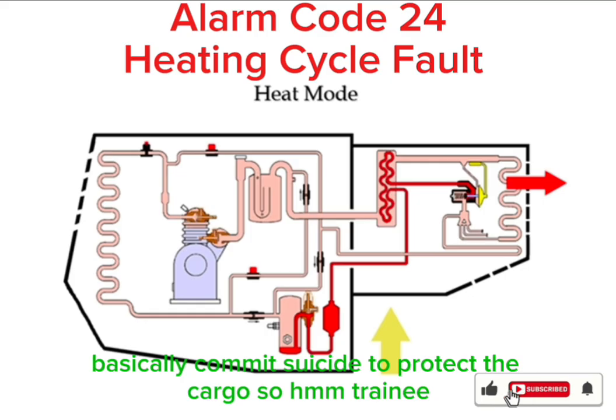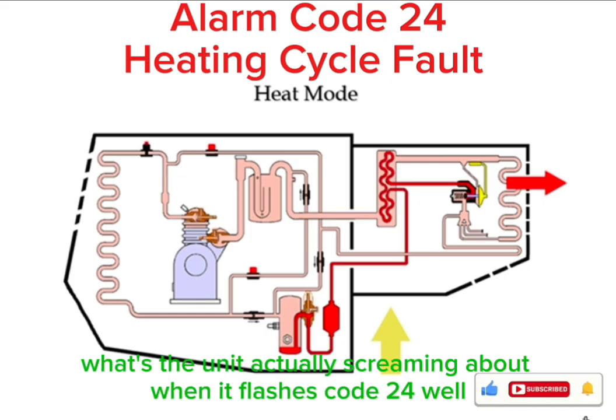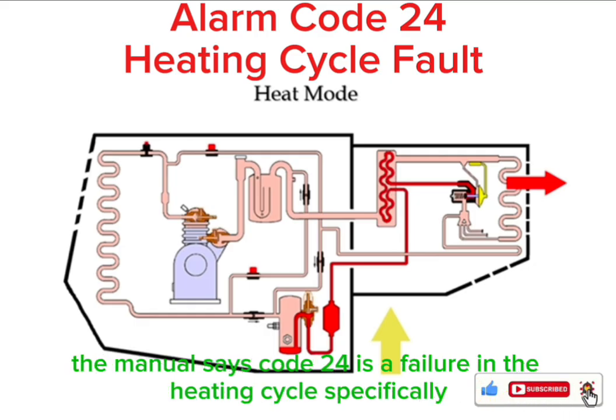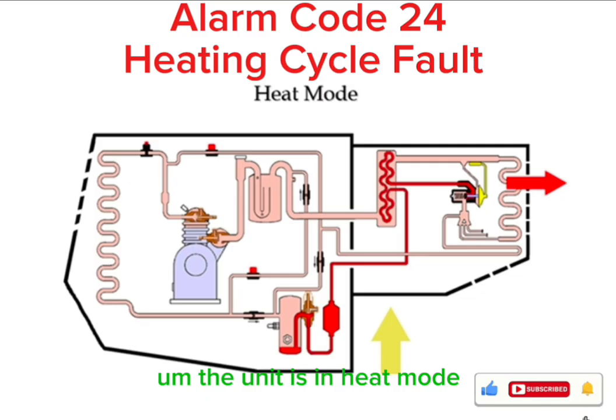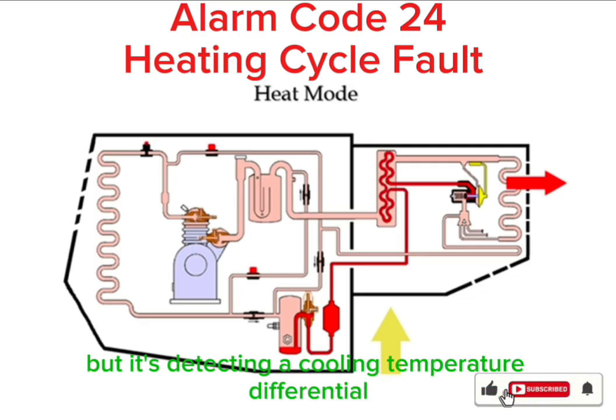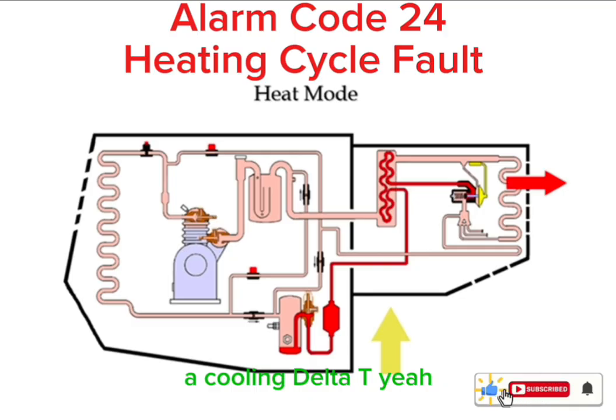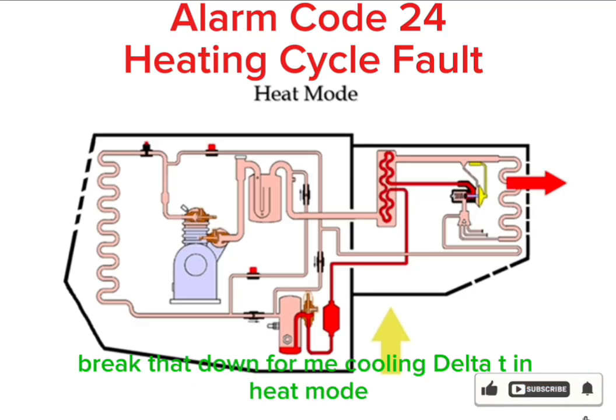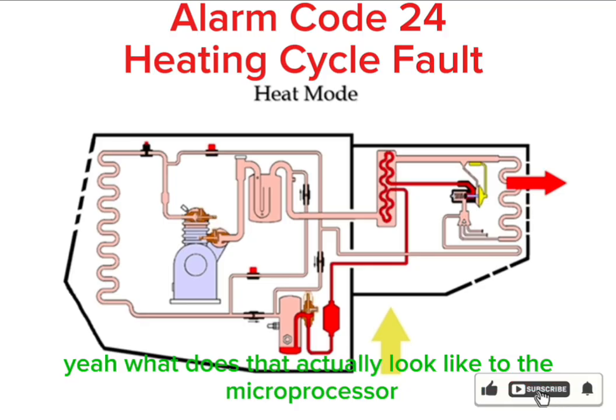So, trainee, walk me through the basics. What's the unit actually screaming about when it flashes code 24? Well, the manual says code 24 is a failure in the heating cycle. Specifically, the unit is in heat mode, but it's detecting a cooling temperature differential. A cooling delta T. Yeah, a cooling delta T. Okay, break that down for me. Cooling delta T in heat mode. What does that actually look like to the microprocessor?